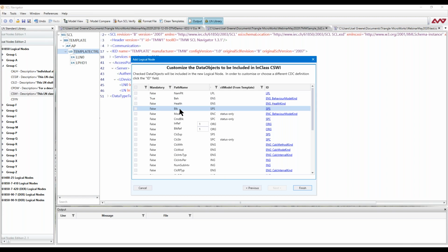In a control, 61850 provides some testing functionality, test modes and blocking modes. And those can only be activated if I have the mod control in the model, which ends up setting the behavior. But to control it at this level, I need the mod, so we'll add that.